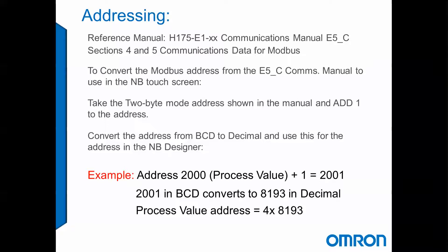For example, the process value, which is address 2000 — we're going to take 2000, add 1 to it, coming out to 2001. We then take 2001 and convert it from BCD to decimal, which equates to 8193. So our actual process value address is going to be 4x8193.